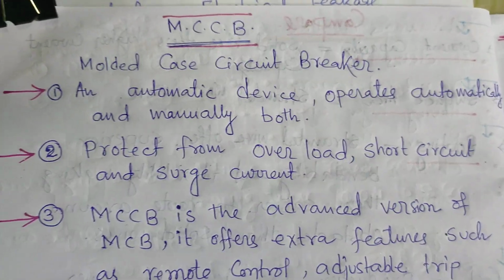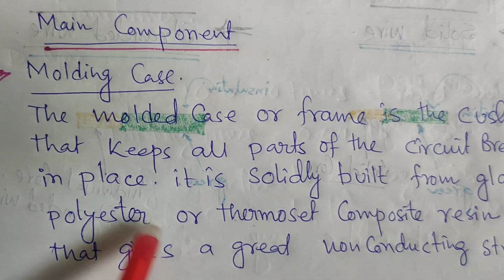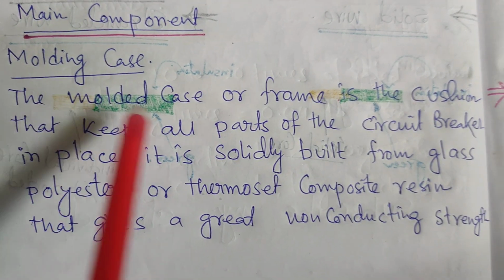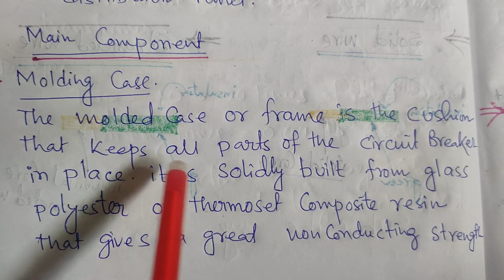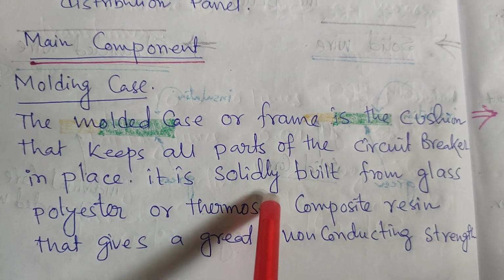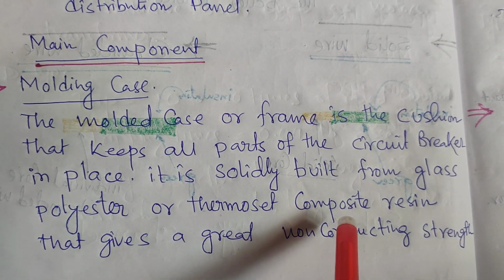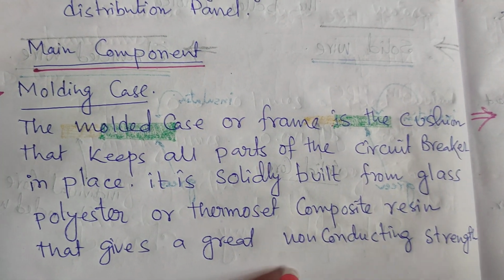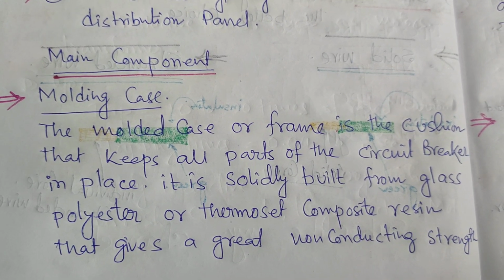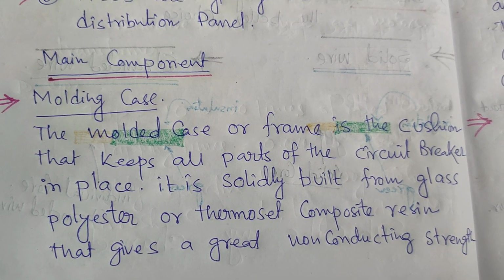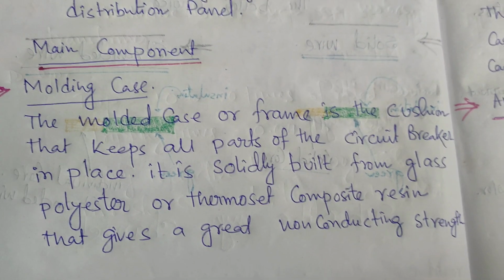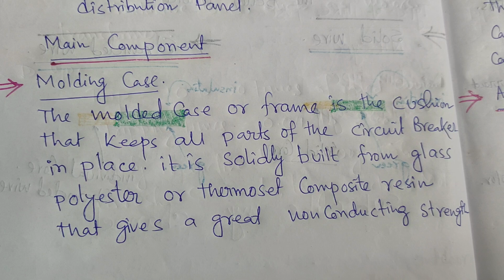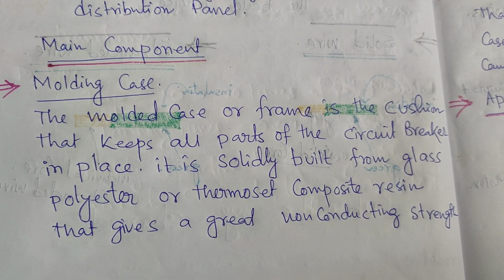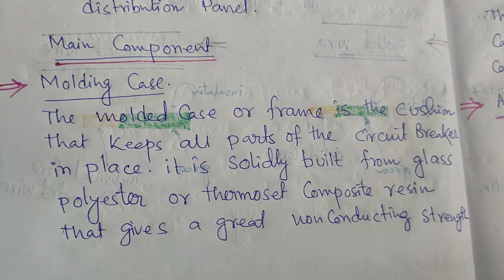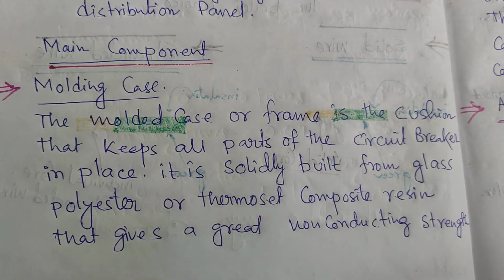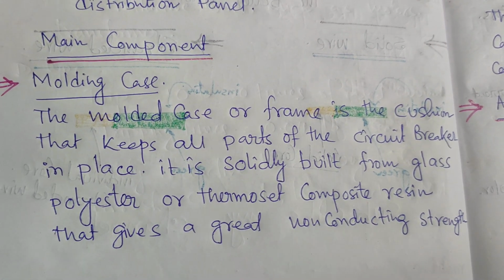Now we start with the main components inside the MCCB. Molding case. The molding case or frame is the cushion that keeps all parts of the circuit breaker in place. It is solidly built from glass polyester and thermoset composite resin that gives great non-conducting strength. The molding case is the upper cover, made of hard plastic, polyesters and thermoset resins. With the help of this, if any arcing or flashing happens, no flashing or fire can come out of the body, because it is totally non-conductive. If you touch it when a fault happens, you will not get a shock. So its non-conducting strength is very high.